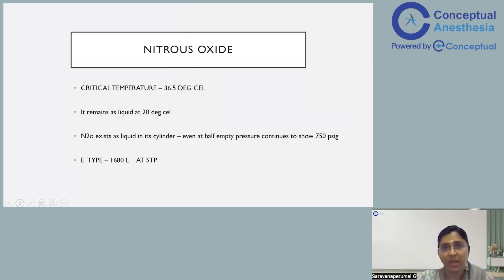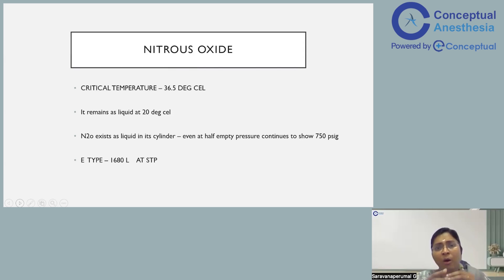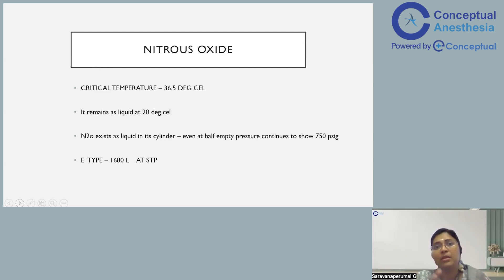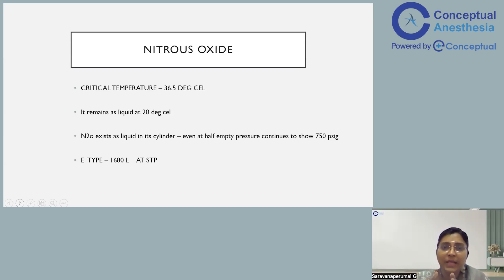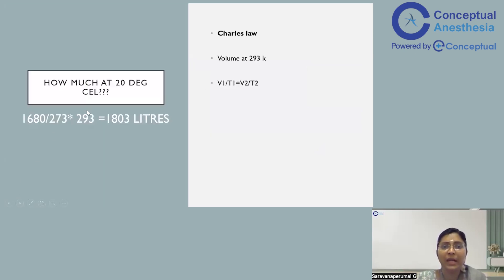What are the practical applications of Charles's law? As mentioned earlier, the critical temperature of nitrous oxide is 36.5 degrees Celsius, so it remains as a liquid at 20 degrees Celsius. In a nitrous oxide cylinder, until all the nitrous oxide converts into vapour, the pressure gauge will continue to show 750 PSIG. Only when the liquid is completely replaced by vapour will the PSIG begin to fall. Therefore, the Bourdon's pressure gauge does not act as a content gauge for nitrous oxide until it is completely in vapour form. In an E-type cylinder, there are 1680 litres of nitrous oxide at standard temperature and pressure.